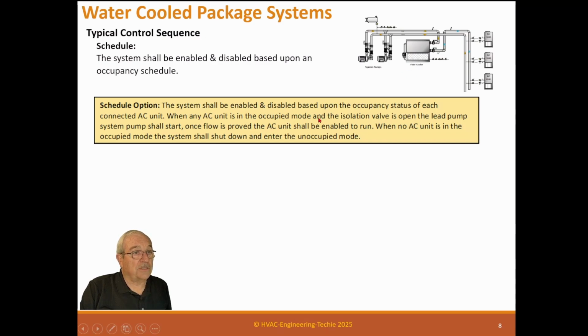So basically this system runs the AC units. When they run, it turns on the central plant. When they're all off, the central plant goes down. It does that by the isolation valve being open and the lead pump starting. Once flow is proved, the AC unit should be enabled to run. When no AC unit is in the occupied mode, the system shall shut down and enter the unoccupied mode. So you can use this as an optional schedule to a hard schedule. But a hard schedule works too.